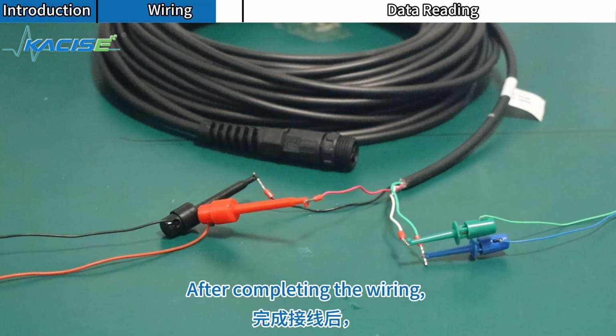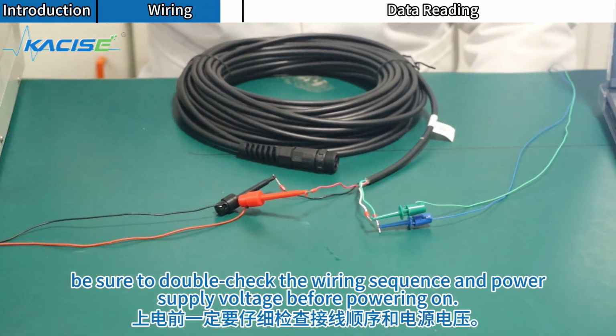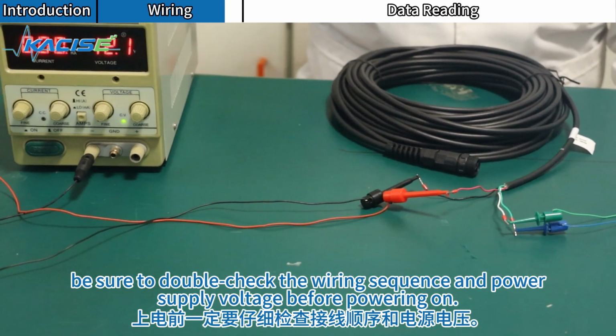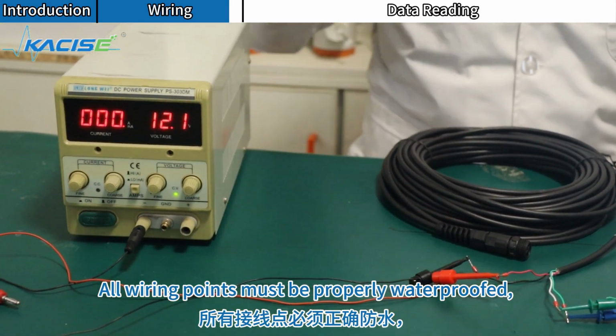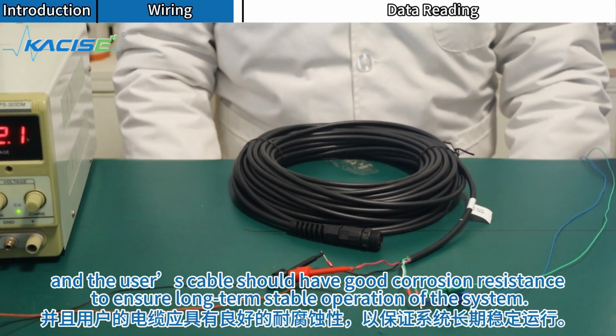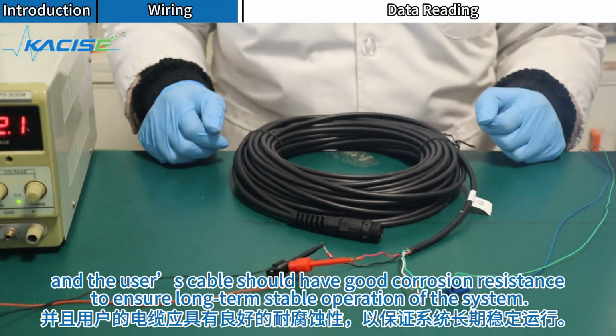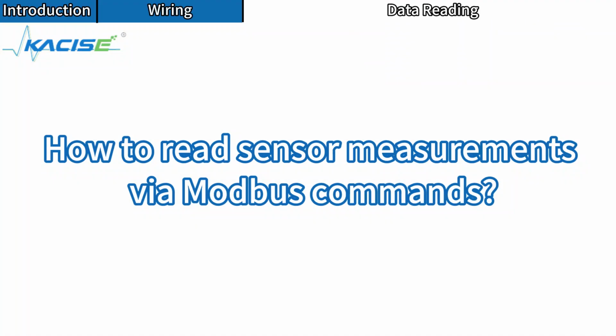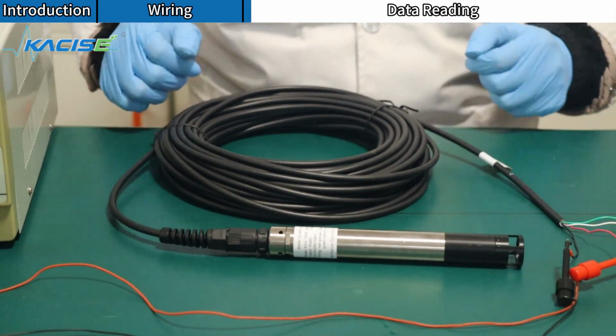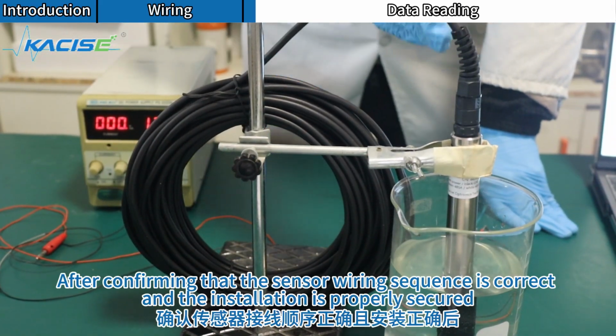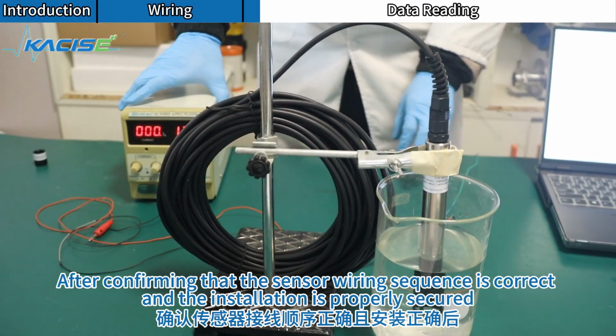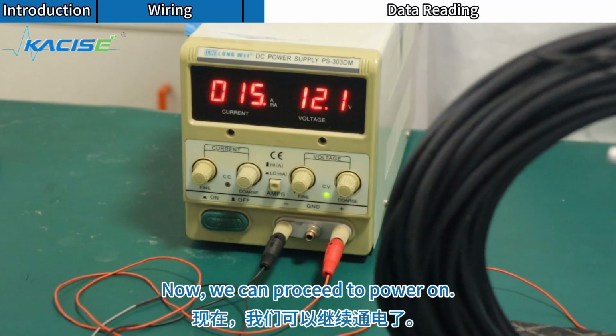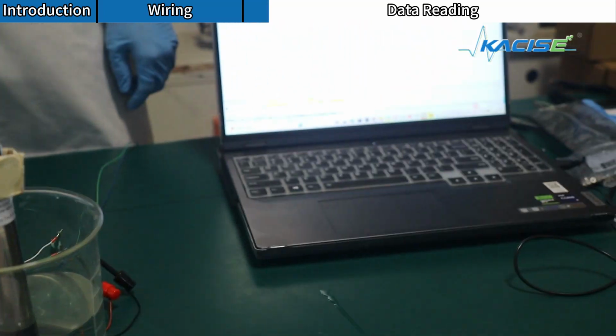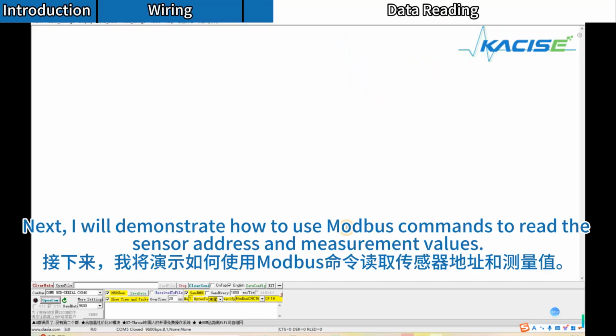After completing the wiring, be sure to double-check the wiring sequence and power supply voltage before powering on. All wiring points must be properly waterproofed, and the user's cable should have good corrosion resistance to ensure long-term stable operation of the system. How to read sensor measurements via Modbus commands. After confirming that the sensor wiring sequence is correct and the installation is properly secured, now we can proceed to power on. Next, I will demonstrate how to use Modbus commands to read the sensor address and measurement values.